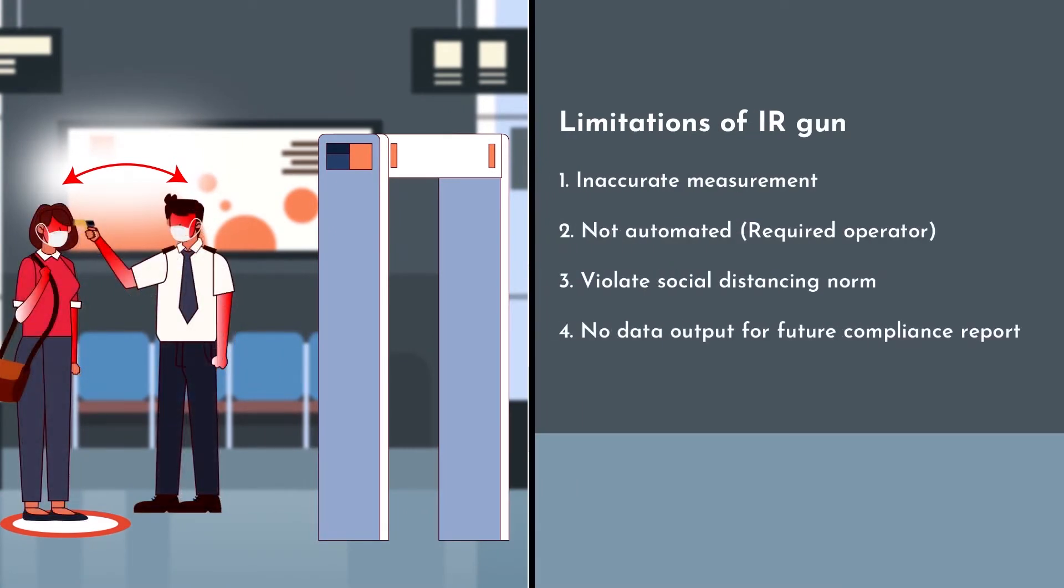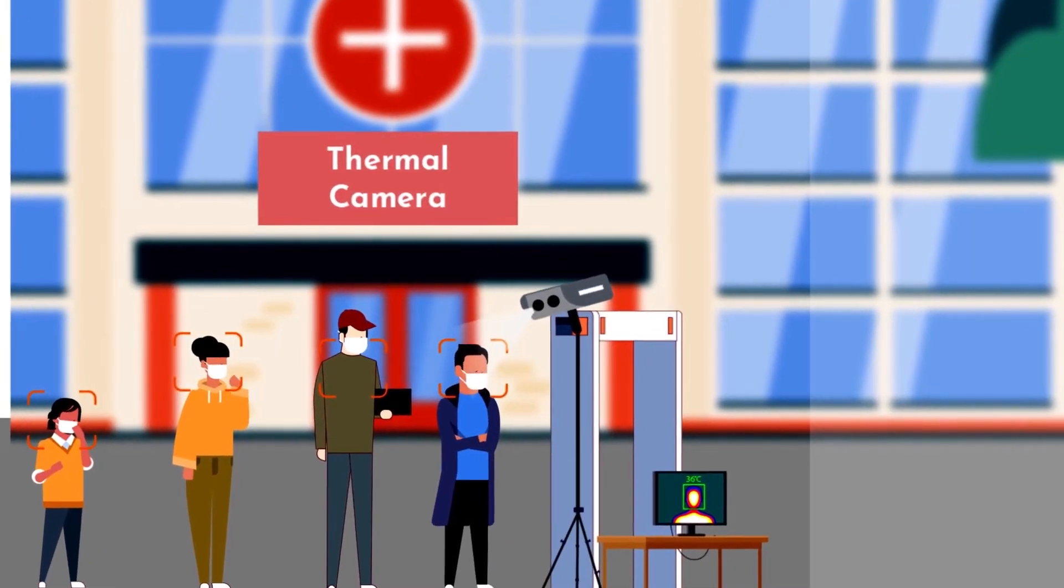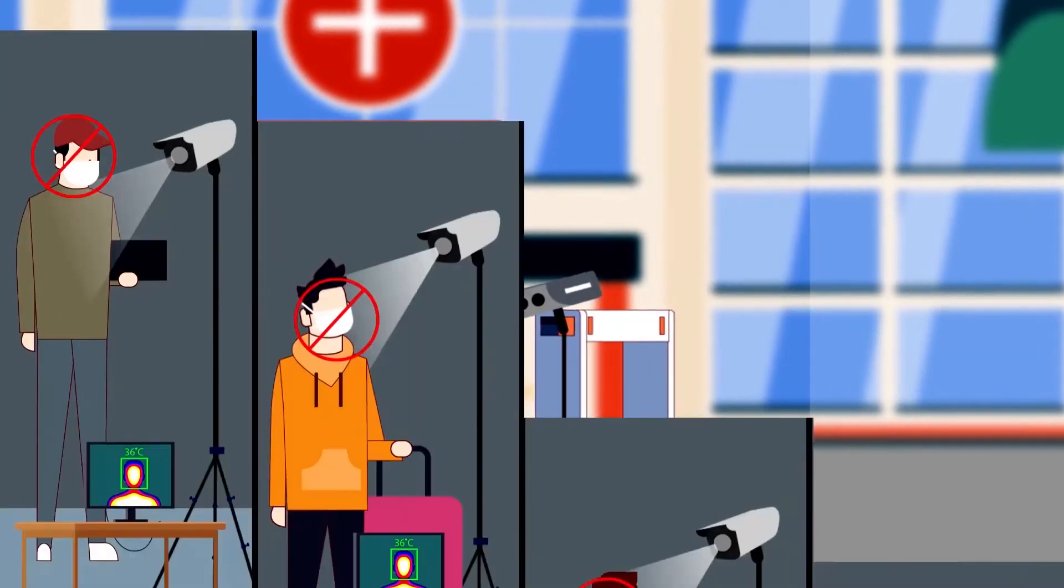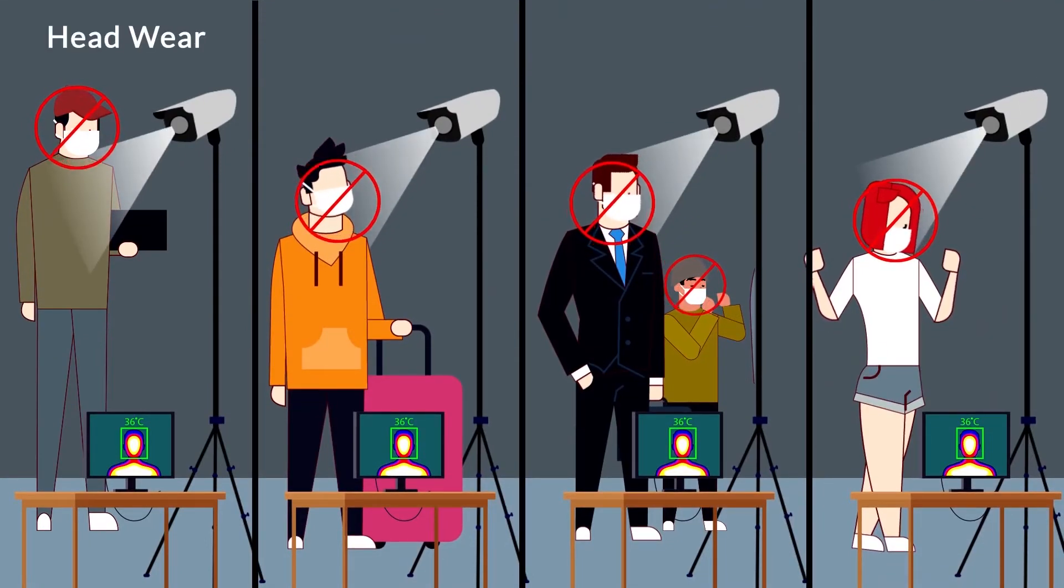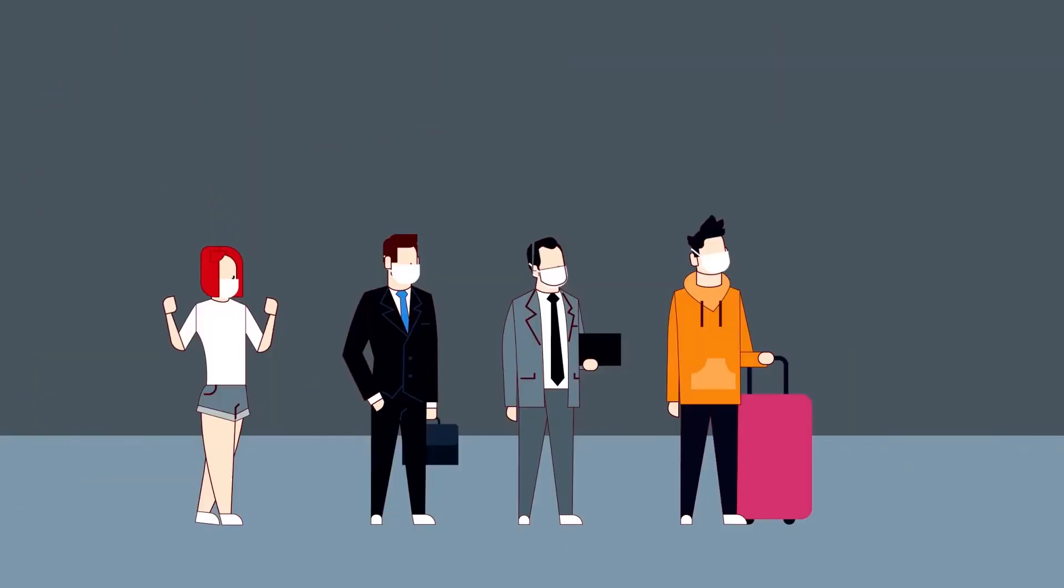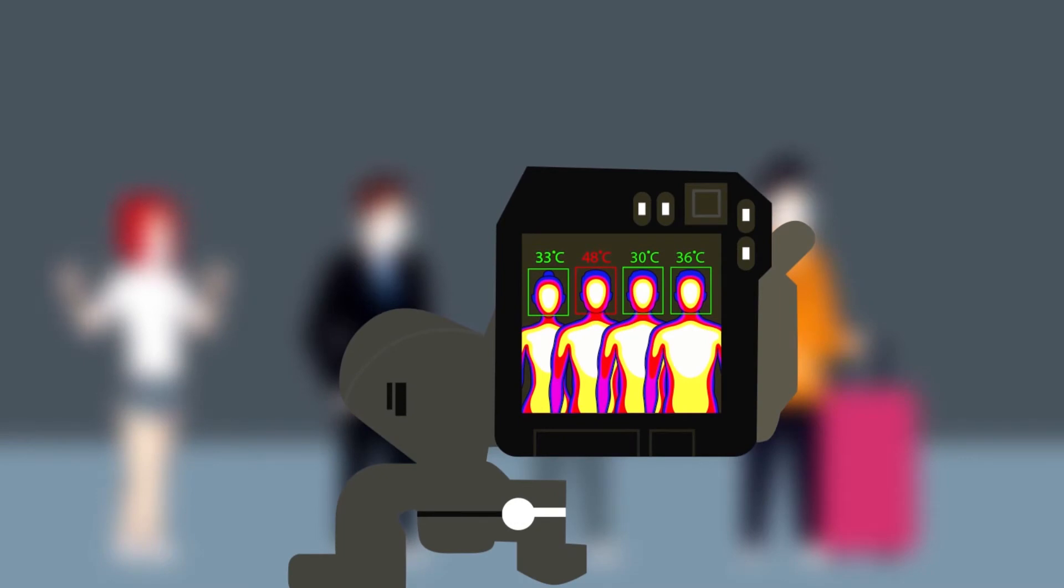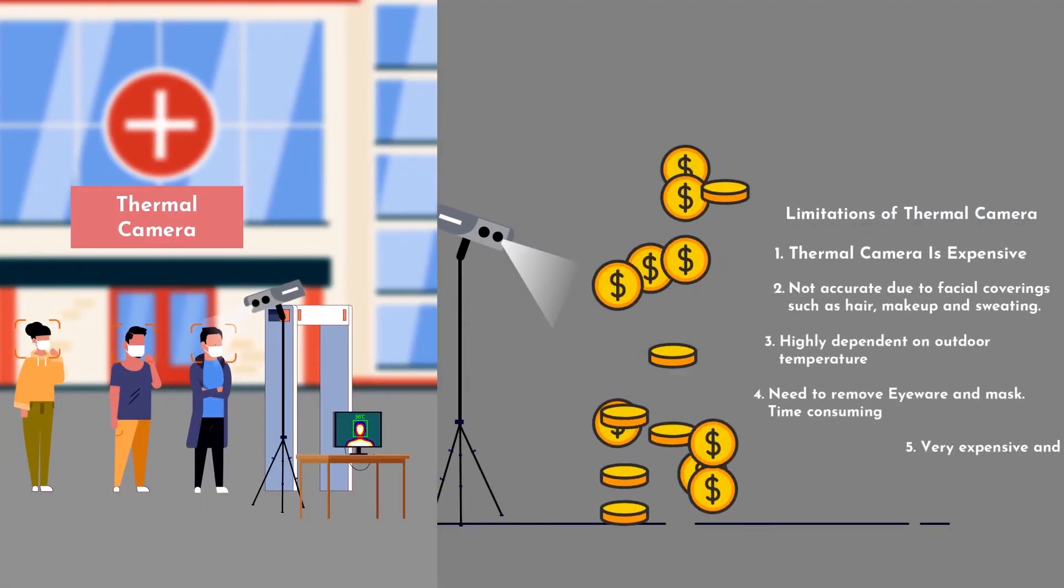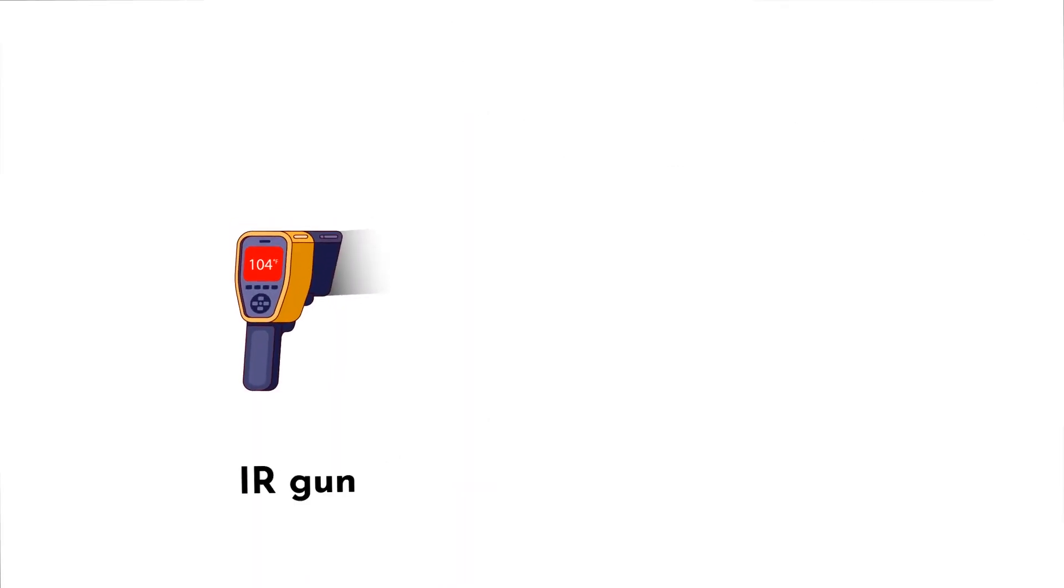The second method is the thermal camera system, which does not require someone to hold a device, but as with any infrared system, does have inaccuracies associated with headwear, perspiration, hair, and types of makeup. In addition, these thermal camera systems bring with them concerns on privacy as well, and are priced thousands more than a single handheld infrared temperature device.